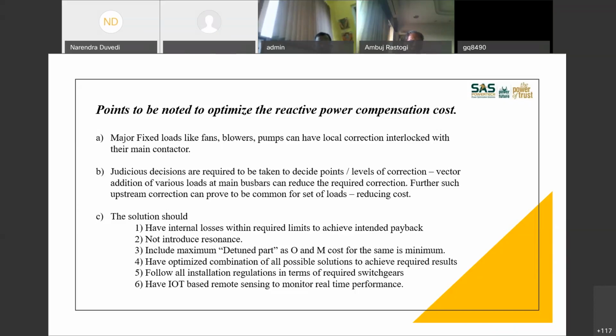Have an optimized combination of all possible solutions to achieve required results, and follow all installation regulations in terms of required switchgears for safety. Many times when we retrofit panels, we get a requirement from our clients asking, can I connect the cable to the incoming of the breaker, and such things. So electrically they are unsafe. So whatever you are spending in the project, if you spend for a proper disconnector, you create a safe installation as well.